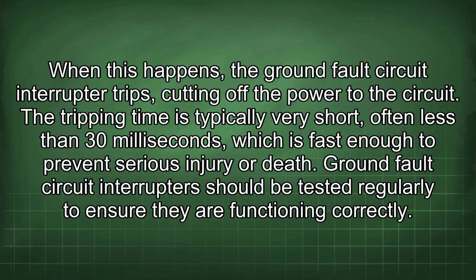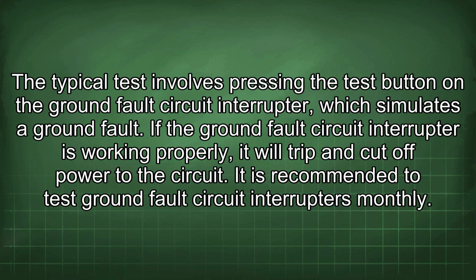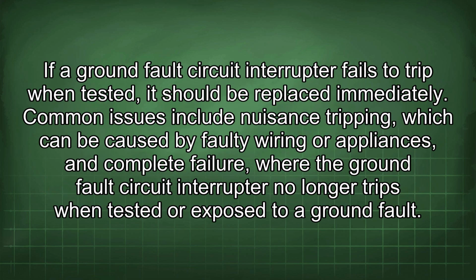Ground fault circuit interrupters should be tested regularly to ensure they are functioning correctly. The typical test involves pressing the test button on the ground fault circuit interrupter, which simulates a ground fault. If the ground fault circuit interrupter is working properly, it will trip and cut off power to the circuit. It is recommended to test ground fault circuit interrupters monthly. If a ground fault circuit interrupter fails to trip when tested, it should be replaced immediately. Common issues include nuisance tripping, which can be caused by faulty wiring or appliances, and complete failure, where the ground fault circuit interrupter no longer trips when tested or exposed to a ground fault.